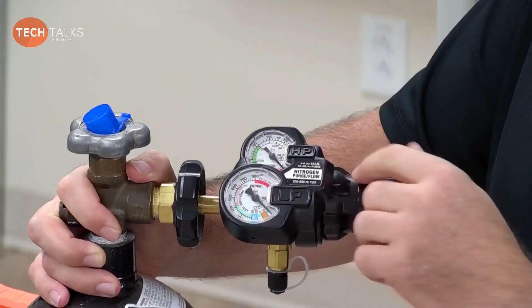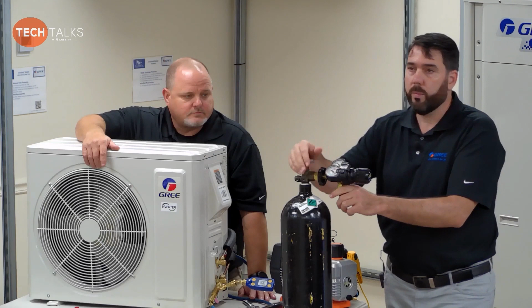Yeah, it's very versatile. So the big thing here is these systems' high pressure cutout is around 600 psi. Don't be afraid to put enough nitrogen pressure on this to actually find a leak if there is one. If you put 200 psi on it, you're likely to not find a leak that is going to leak at 400 psi. So we kind of go with the 400 psi range. It's a safe range, but you're also going to find any leaks.